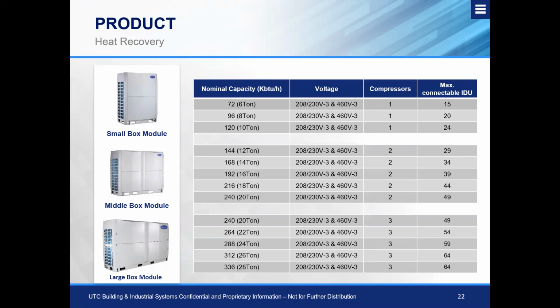Now, as we step up through a 12 through 20-ton, we're going to move to our mid-box module, and you'll notice on there that the compressor amount increases, obviously because we have more tonnage that we're trying to facilitate. Okay, and of course, as we step up the tonnage, that maximum connectable indoor unit number does rise with the tonnage as well. And then finally, as we go through our 20 through 28-ton applications, we'll move into our large box module, which again adds another compressor and more connectable indoor units. Our maximum connectable indoor units on one centralized outdoor unit, for example, on a 26 or a 28-ton unit, is going to be 64 units.